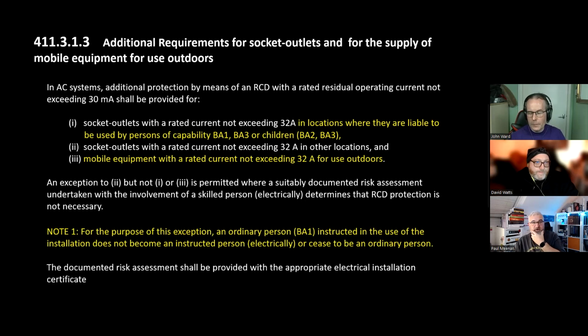411.3.1.3, additional requirements for socket outlets for the supply of mobile equipment for use outdoors. This is an interesting one because it says an RCD not exceeding 30 milliamps shall be provided for socket outlets up to 32 amp, which went up to 32 amp in the last edition, i.e. the 18th. But it adds in locations where they're liable to be used by persons of capability BA1, BA3 or children, BA2, BA3. It then also adds, and this is a new addition to the regulation, mobile equipment of a rated current not exceeding 32 amps. So they're really closing down on everything up to 32 amps, RCD.